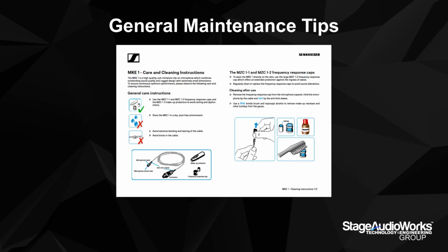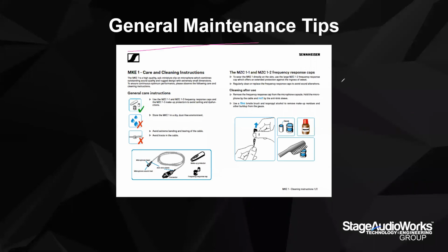Just some general maintenance tips. The picture I have here is the care and cleaning instructions that come with the Sennheiser MKE1. A lot of manufacturers also release documentation like this. So don't just use chemicals that you don't know will work properly. Check if the manufacturer has a document like this. This can save you a lot of headache, like using a chemical that will degrade the cable or break the capsule. So just consult the manufacturer user manual for some of those things.